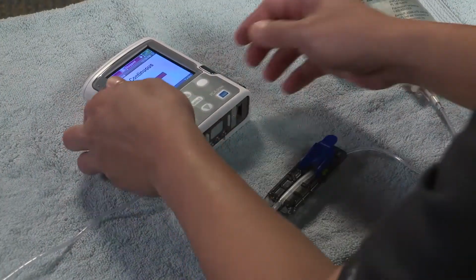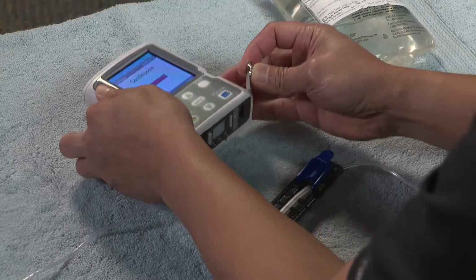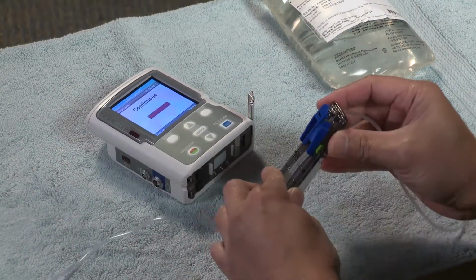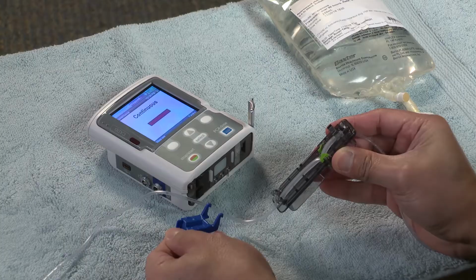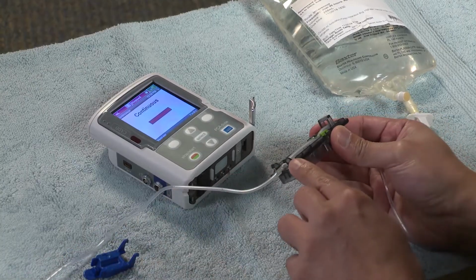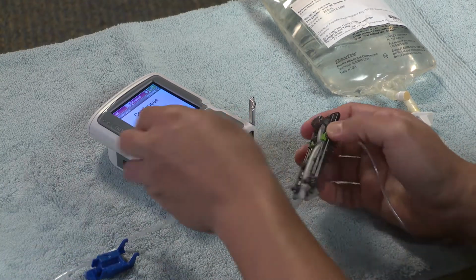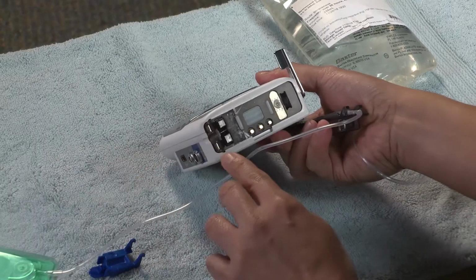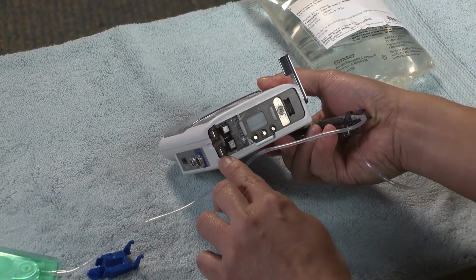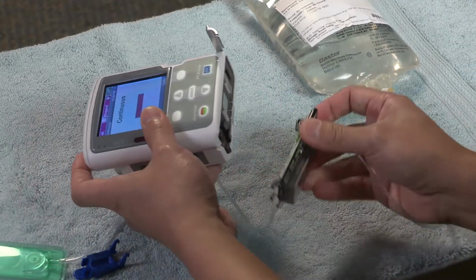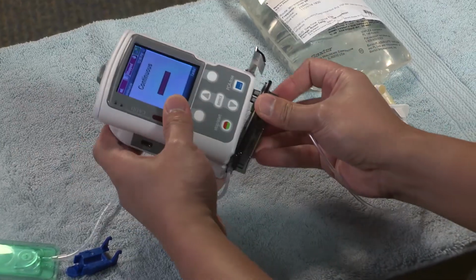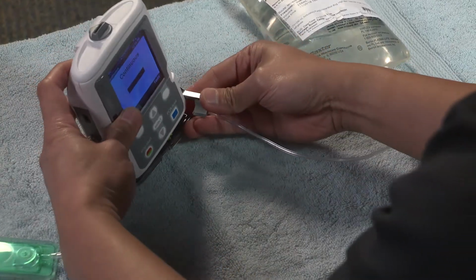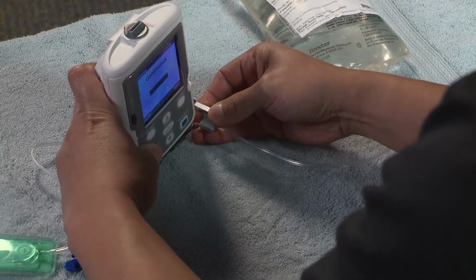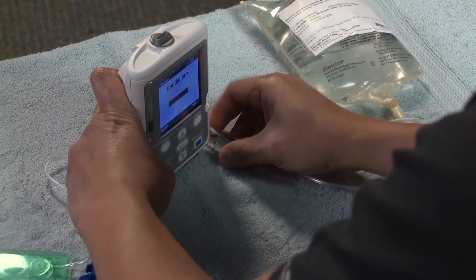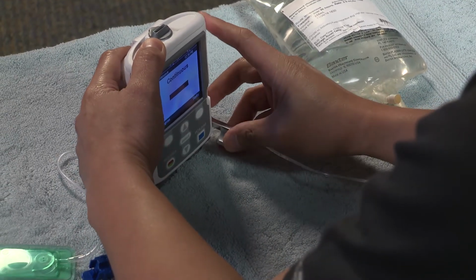With the pump powered on, open the cassette latch. Remove the blue clip from the cassette. You will see 2 plastic prongs. These fit into the bottom of the CADD pump under the metal rods. After fitting the prongs in, place the cassette against the bottom of the pump. Turn the pump over and press down firmly. Lift the cassette latch handle into the closed position.